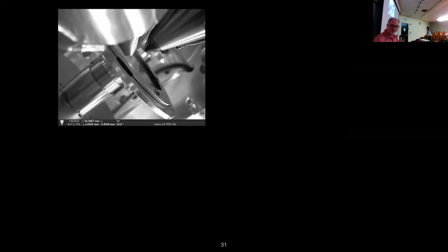So here's another view of our gasket. You can see there's a hole when we're tilted to 52 degrees. We're now normal to the ion beam. There's probably around 200 microns of spacing between the sample and the very expensive electron lens. So we really have to make sure that we are on top of setting eucentric height. So eucentric is a point about which you can tilt and you do not have image translation. I will probably hate myself for saying, take out your phones, people, if you have them, and look at a spot. And when you can find a spot where you can tilt and not have a translation, that's eucentric.